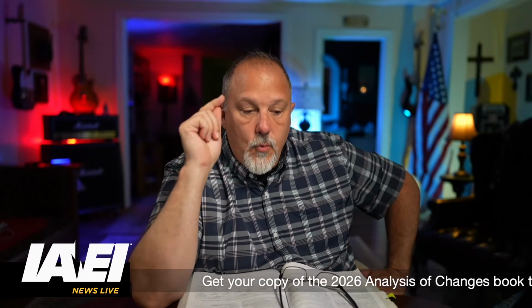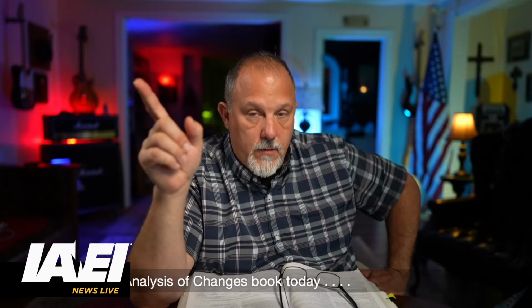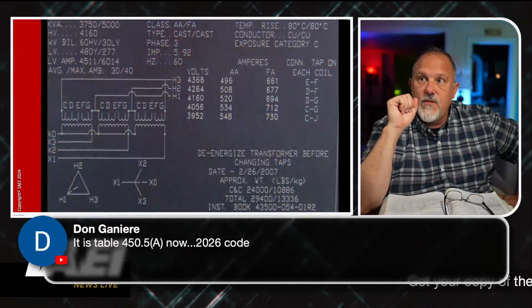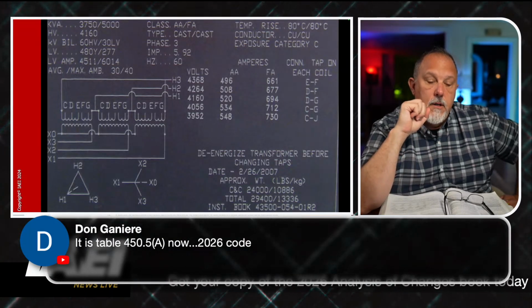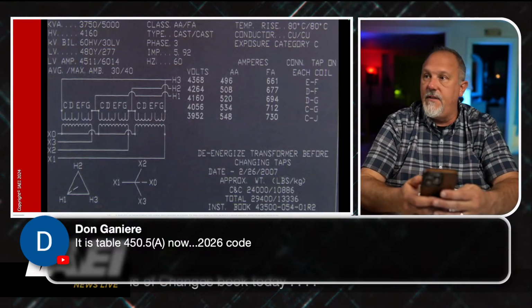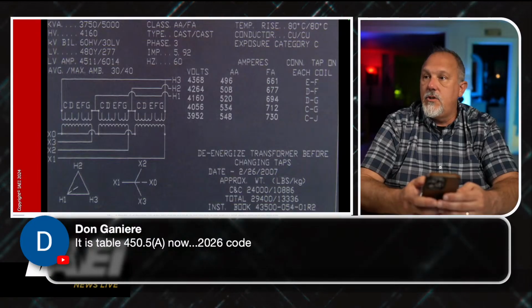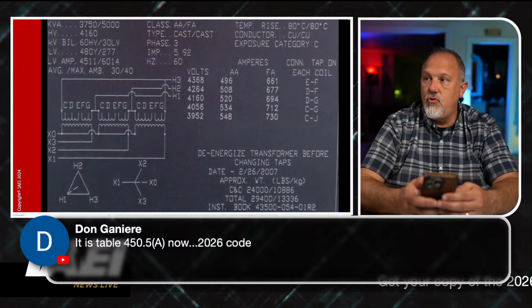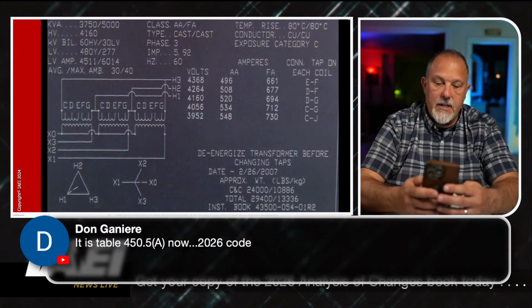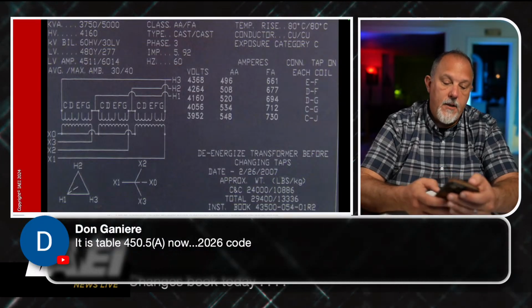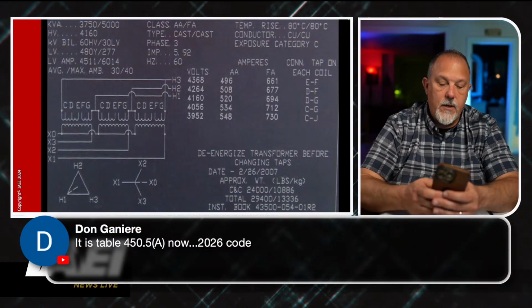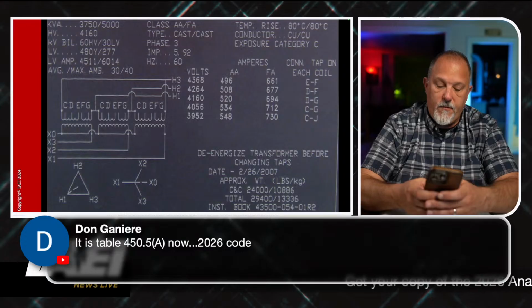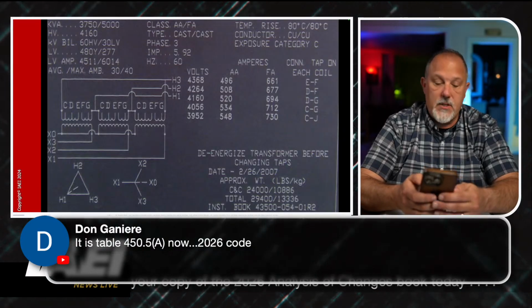Okay, and remember the process. The process is you will first get the information from the transformer. You'll determine the full load amps on primary and secondary. Then you'll use this table. Now, let's say, for example, I'm dealing with this transformer that has 2 kVAs. The kVA on the primary for 3750 is 3750. So let's calculate what's the full load amps. Let's walk through it. 3750 divided by the square root of 3 divided by 4.16 is 520 amps.